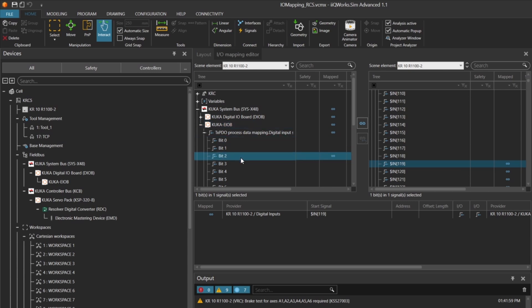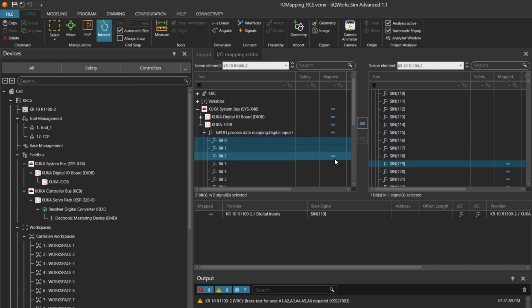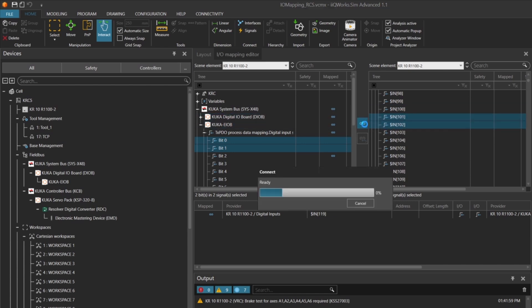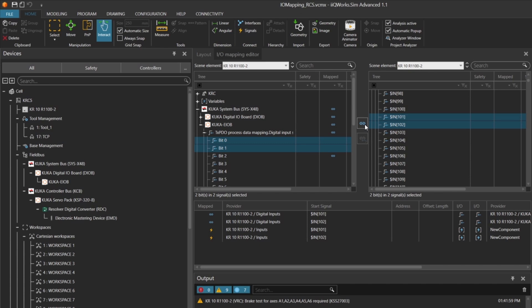At first, the mapping didn't work correctly. That's usually a sign that the connection wasn't fully established. So we double-checked the inputs 101 and 102, and after retrying, the mapping was successful. You can now see the blue symbol indicating that the signals are correctly connected.